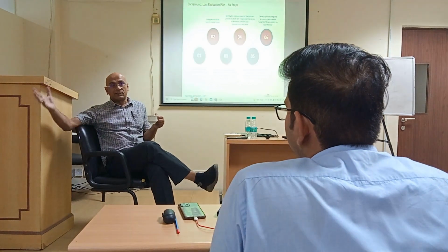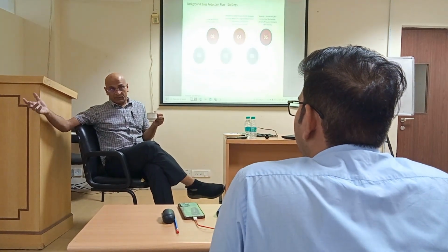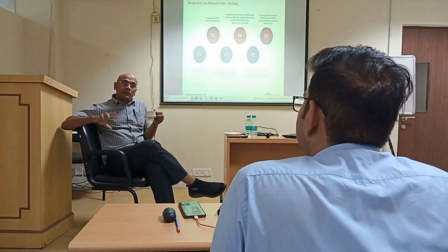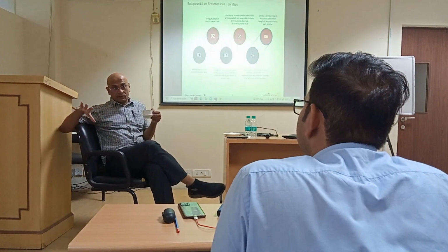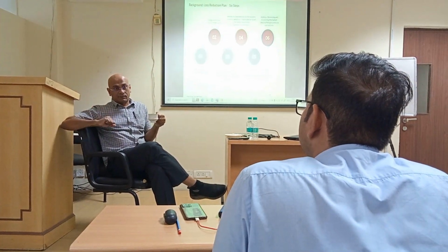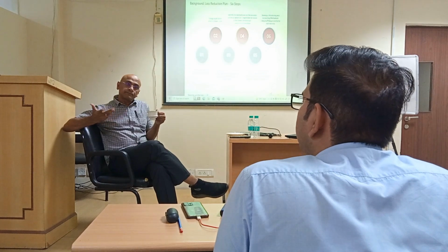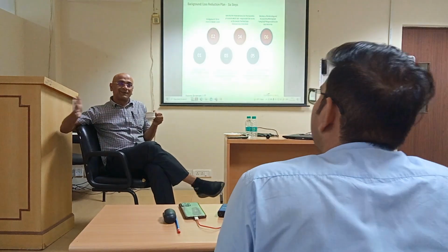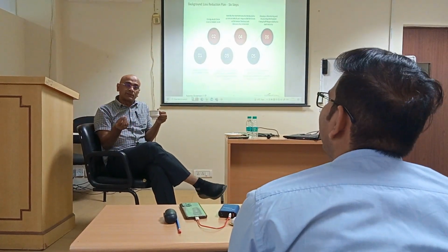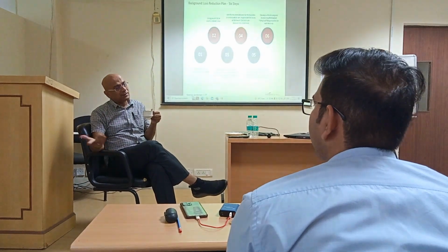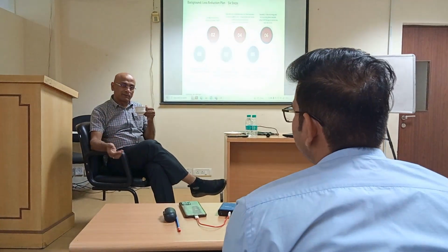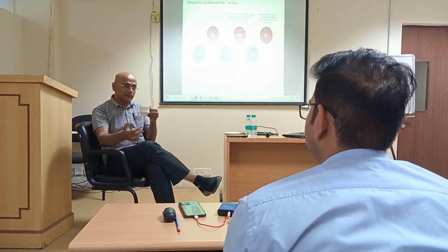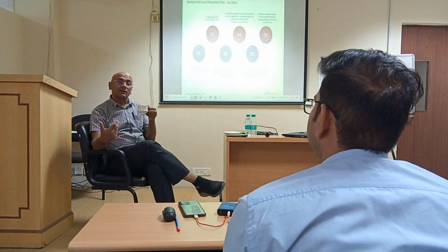So there is a very clear difference between the substation meter reading and the billing meter. Then we could find out that the CTPT set which was used, they had tampered with it. And that too, they didn't use the 0.2 class which is used for metering, not even that, I'm talking about class one level below. So the CTPT ratio was tampered. You can tamper the CT and then the meter will show a wrong reading, because these are HT meters. Whatever the CT or PT gives is what you are going to record. So these are the kind of experiences we had.